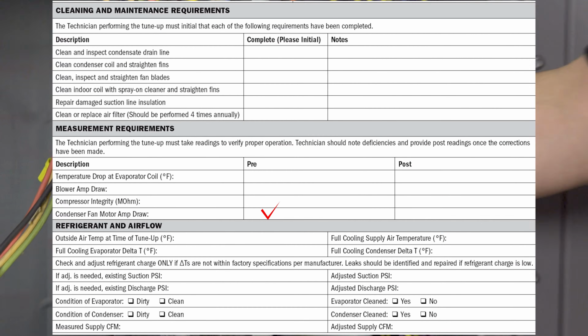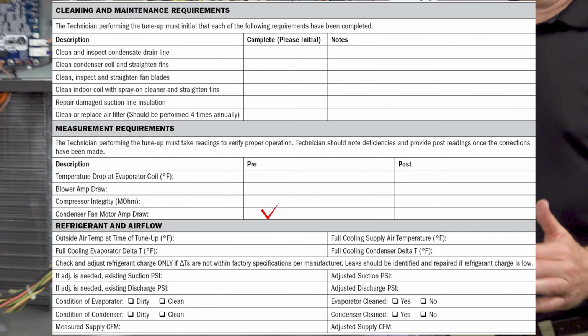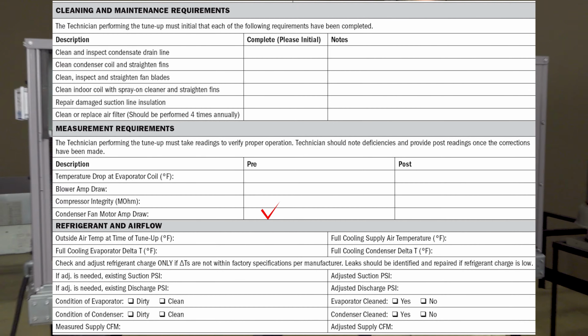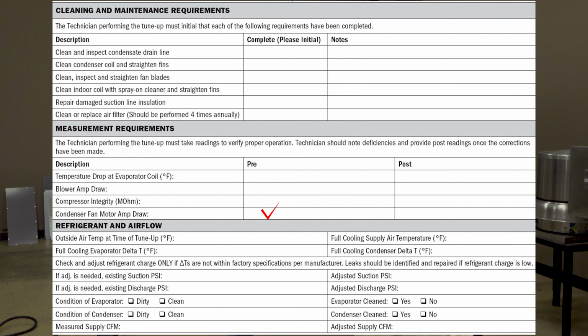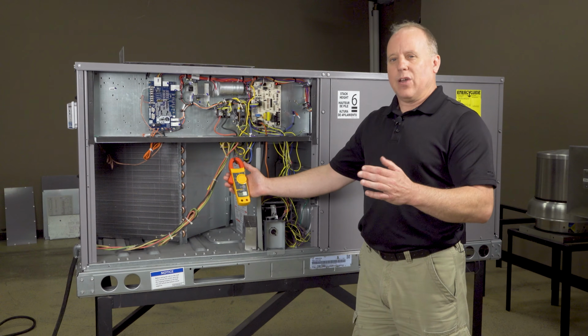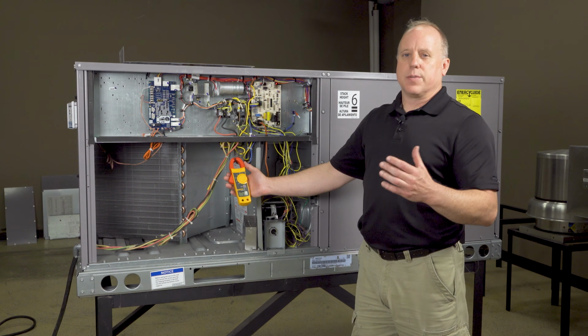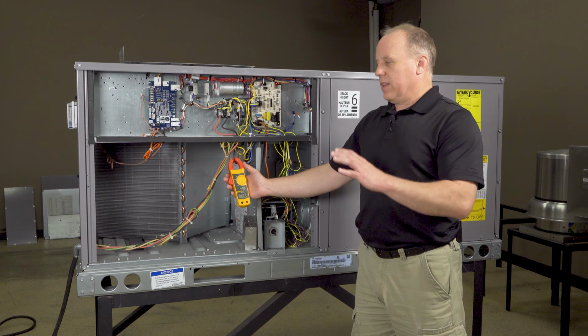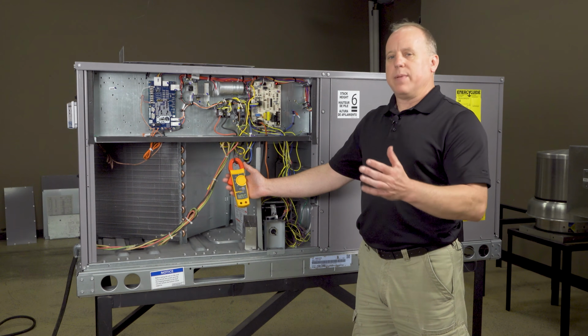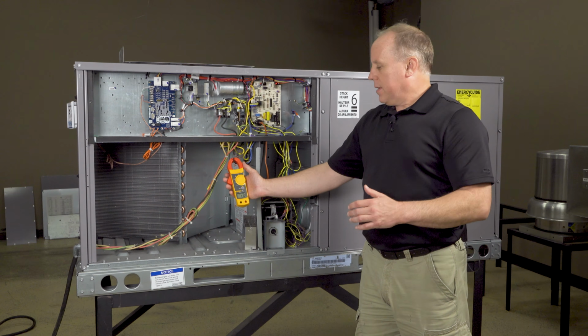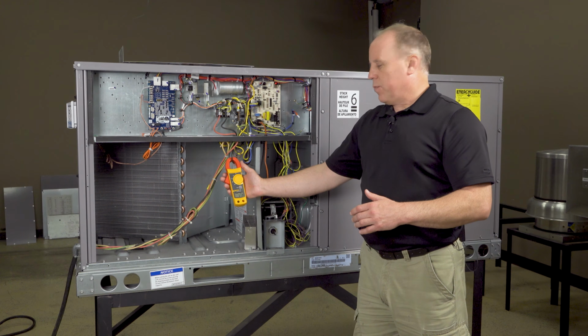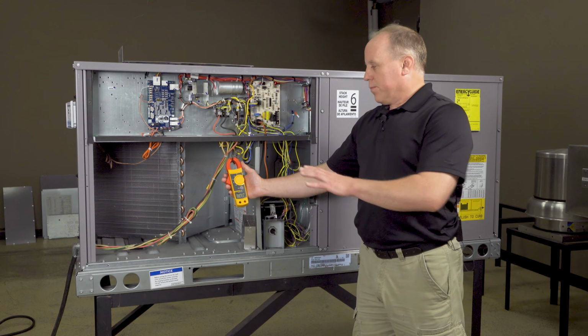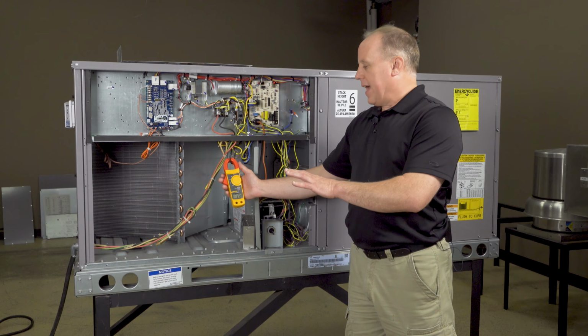So that's pretty close to the range that we should be running. We never want to be over the range or drastically over, maybe slightly depending on load, depending on conditions, depending on heat. But ideally, we're at that range or maybe slightly below. So we take a look at that. We make sure we're good. Right now, we're running fine on this one.